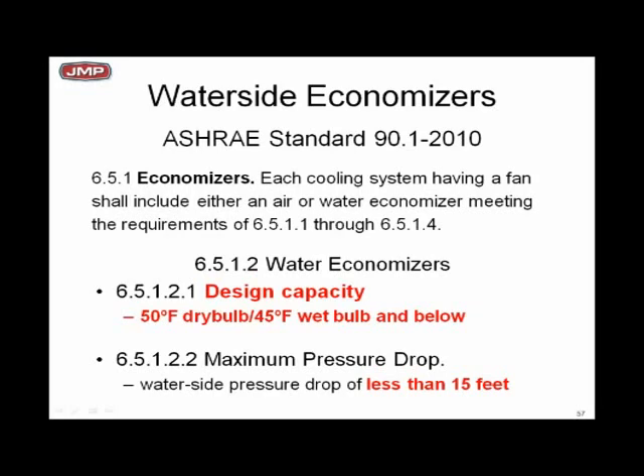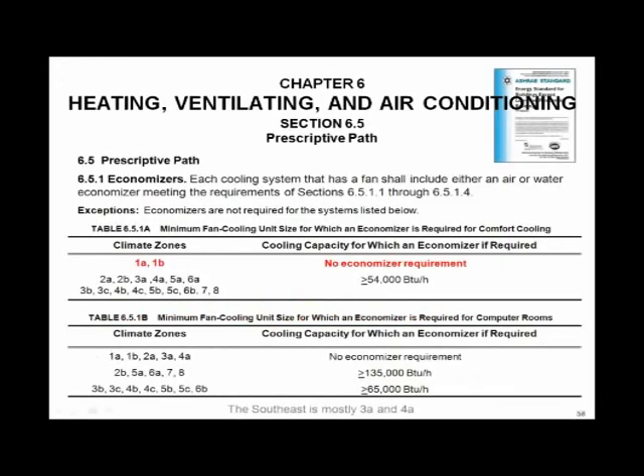But what's new is what? Look at what's in red. The design capacity of the economizer shall be 50-degree dry bulb and 45-degree wet bulb and below. Wow, there's a statement of actual load. And you see some other comments about pressure drops allowed through the heat exchangers that you're using. Let's go a little deeper on this economizer thing. Where do you have to have an air side or water side economizer? And again, we won't be speaking about air side, but where do you have to have it in your design? Per DOE, per the energy code, per ASHRAE 90.1 2010.